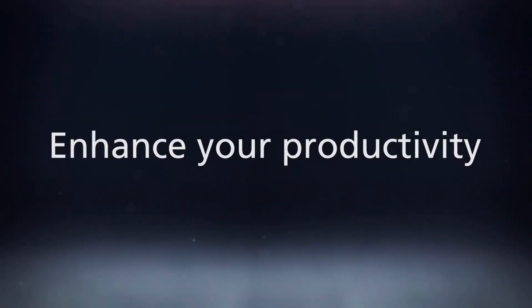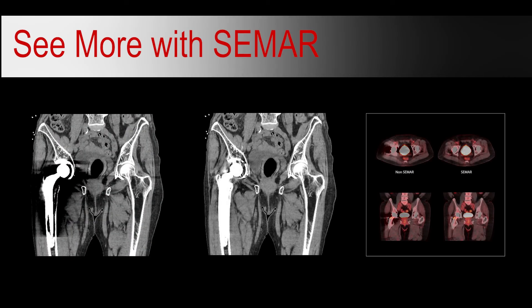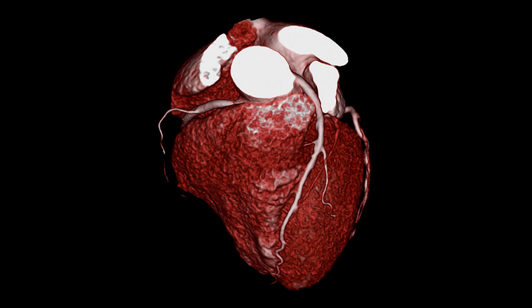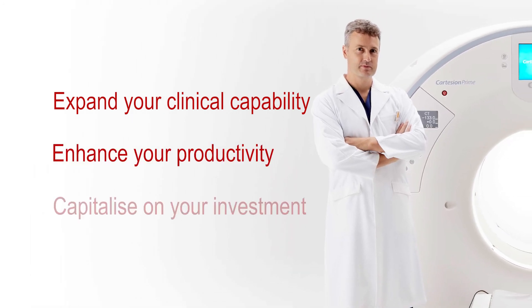An additional business benefit is that the Cartesion Prime leverages Canon's high-end Aquilion Prime SP CT to combine advanced PET technologies with premium CT features. Featuring Canon's Pure Vision Detector — the industry's smallest 0.5mm detector elements for high-resolution imaging — our superior metal artefact reduction technology SEMAR to improve visualisation of metal artefacts supporting bone and adjacent soft tissue, and advanced CT features like sure subtraction iodine mapping, AiCE deep learning reconstruction and cardiac application support. With this powerful PET and CT duo, you can expand your clinical capability, enhance productivity and better capitalise on your investment.